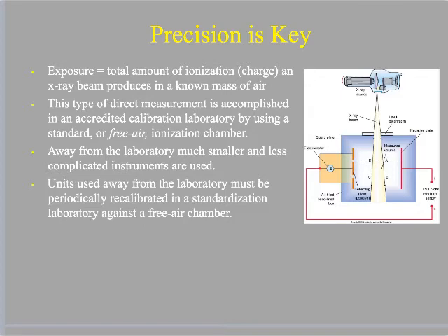So annually or every 13 months, we're going to have to send our Geiger counters back to that lab, to measure it and make sure that this Geiger counter is still as precise as this measure that we have here in the controlled situation. So we have to occasionally standardize or recalibrate what we're doing.